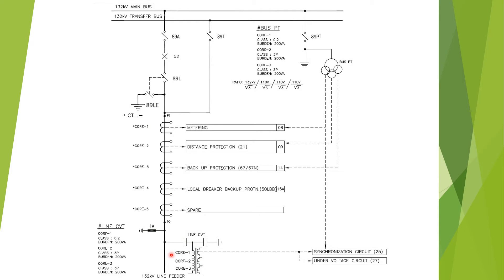In the case of a 220kV or 400kV line, there exist three line CVTs for each phase. In the case of a 132kV feeder, there exists one CVT, typically on the blue phase. If the line is charged from the remote end substation, there will be voltage at this point. In this case we cannot close the line earthing switch, otherwise a dead short will occur. To avoid this, interlocking is provided from the CVT secondary input which is taken to the under-voltage relay.